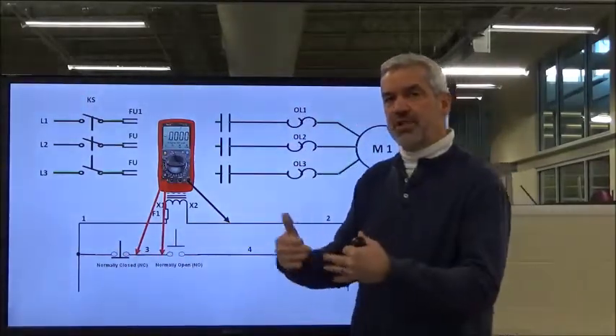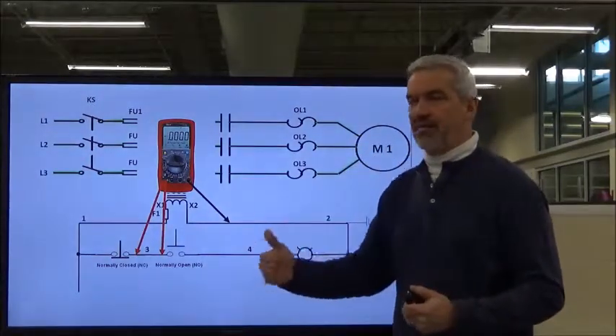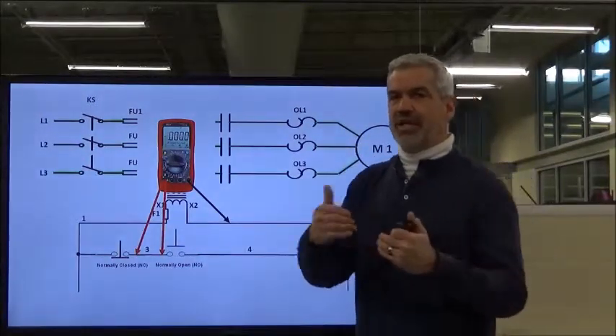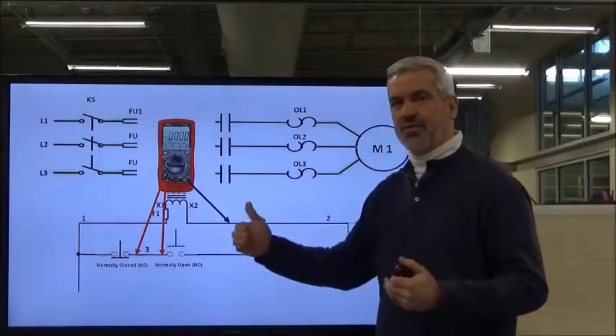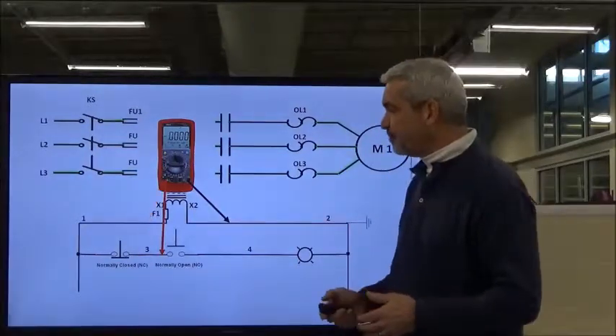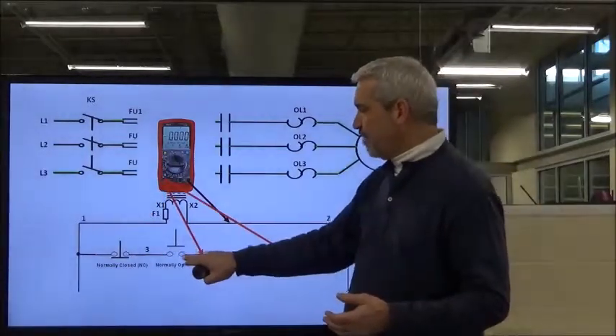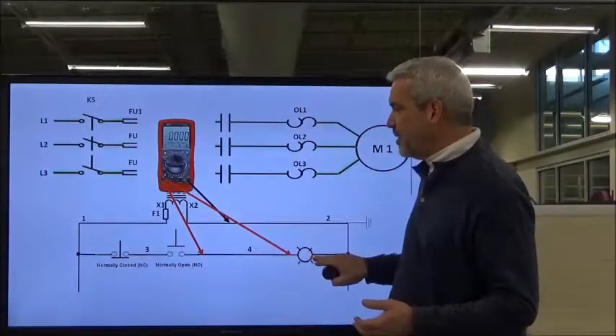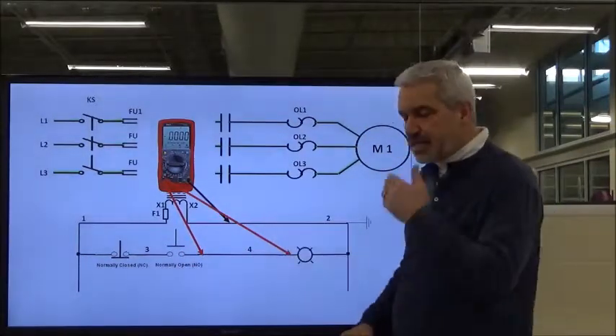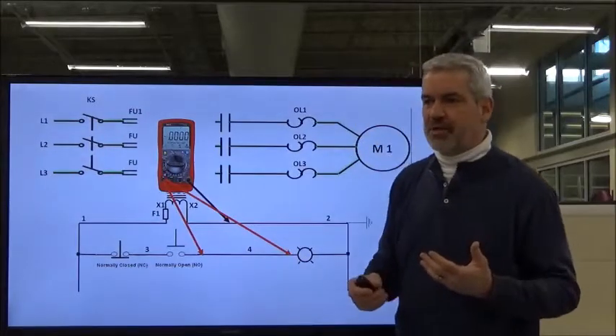So as you can see, we're just checking to see where it's getting to a device, leaving a device, and then doing that with each device downstream. We're going to check it here and continue to check and reference it to neutral. That's one of the safest and most logical ways to do it.